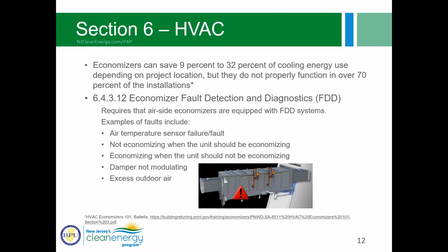All right, so again, this one is targeting economizers, going back to that persistence of savings and ensuring that both the energy efficiency measures and the equipment are functioning properly as intended. Different studies show that economizers can save 9 to 32% of cooling energy use depending on the location, but they often don't function properly in about 70% of installations.